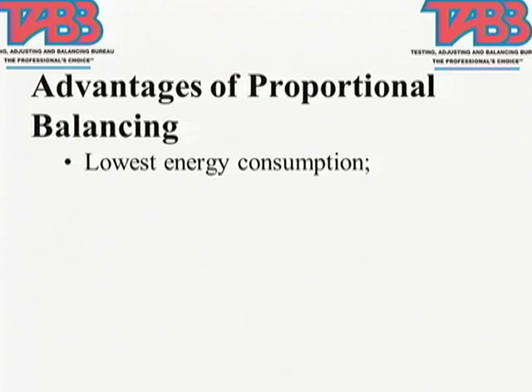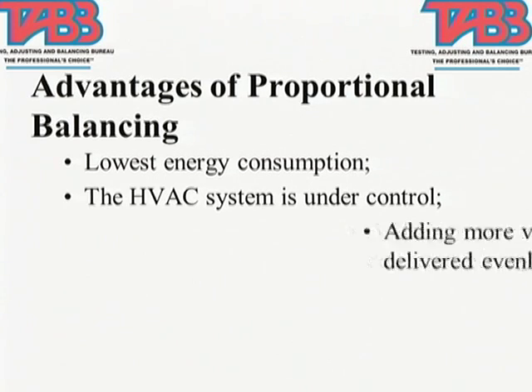And you're laughing because I imagine you've seen this over and over again, and you shake your head at it. And really what it did was it helped out the VFD world because they could come in and say, hey, we can control it with speed instead, and we'll actually finally do something about the issue or the problem. And burn a lot of motors out in the process, exactly right. From not just trimming the impeller, it's working against yourself. Some of the other advantages: it's the lowest energy consumption you can have if it's proportionally balanced and you follow those rules. The HVAC system is under control.